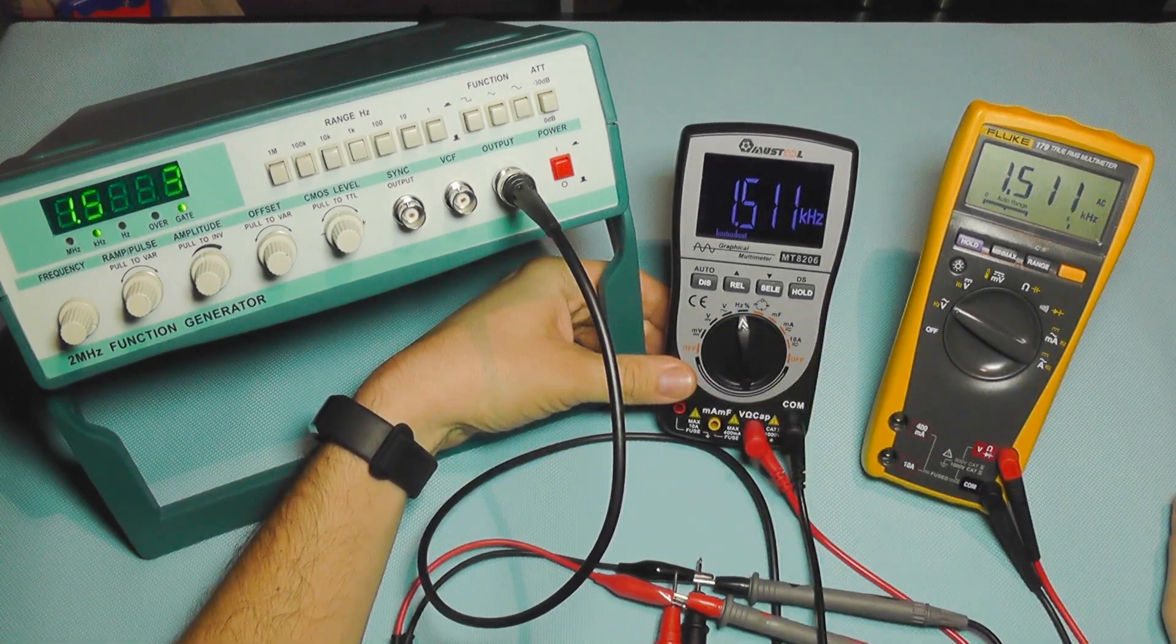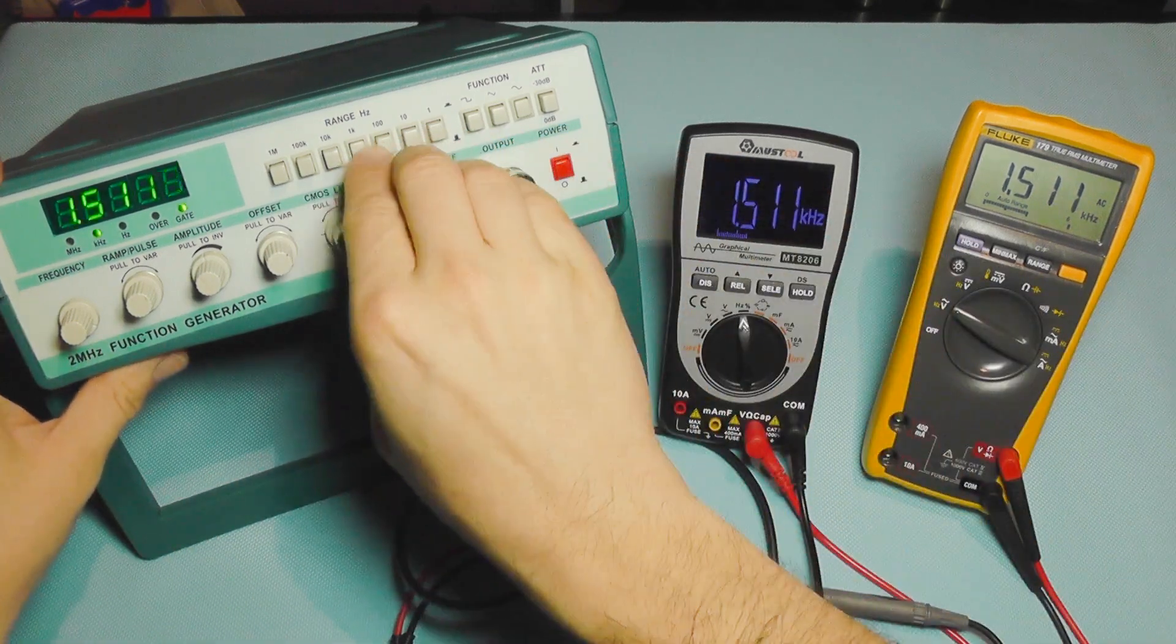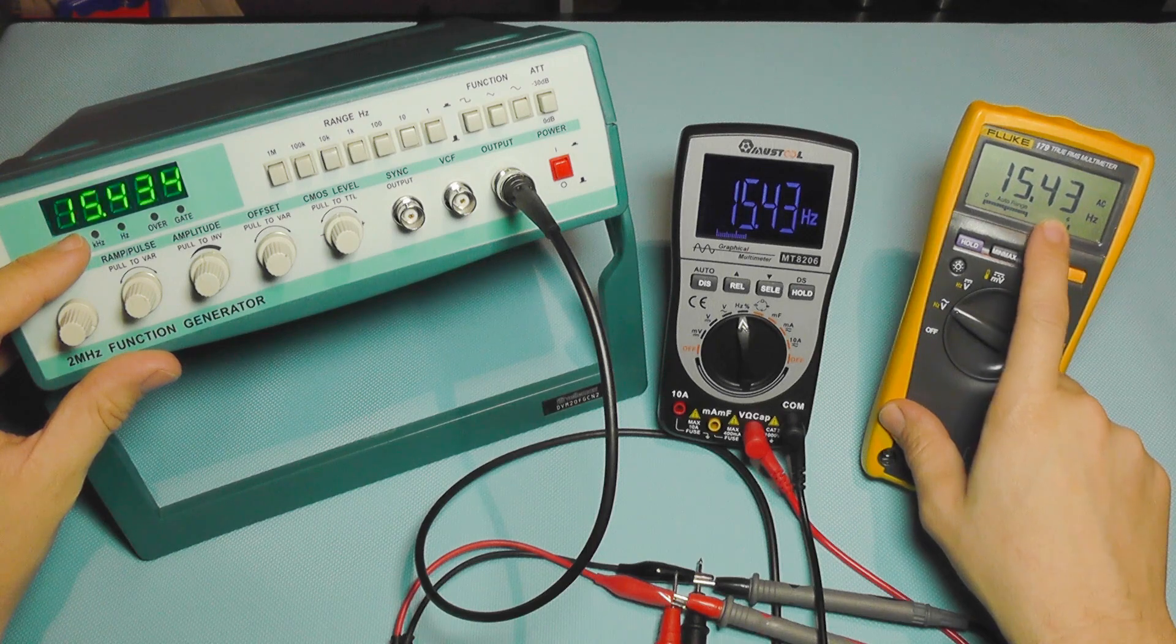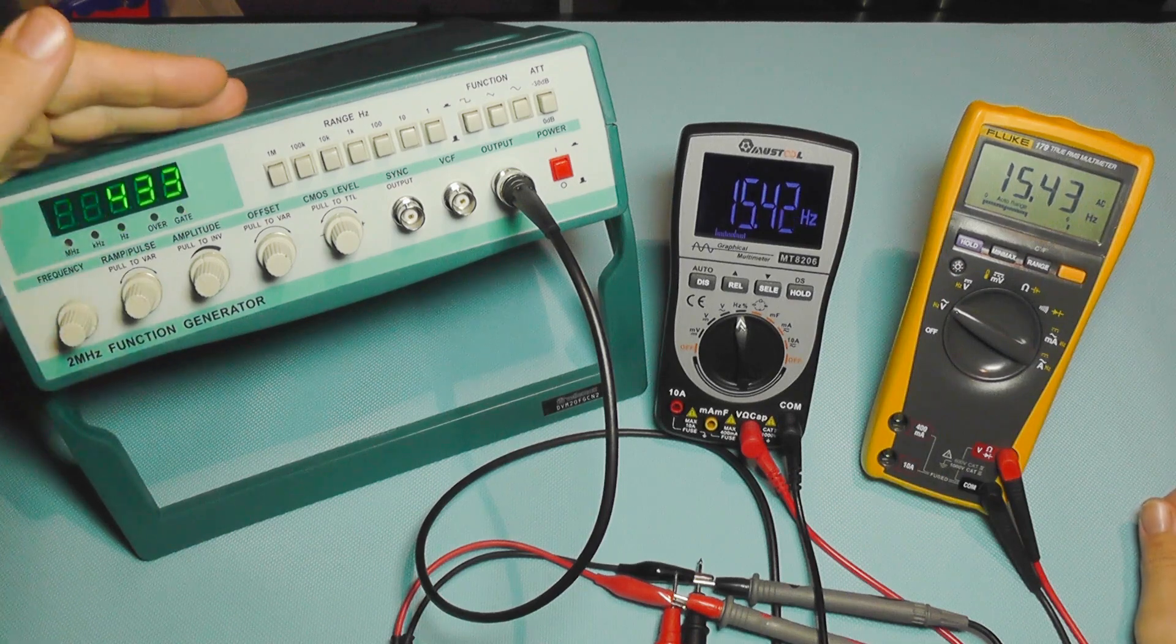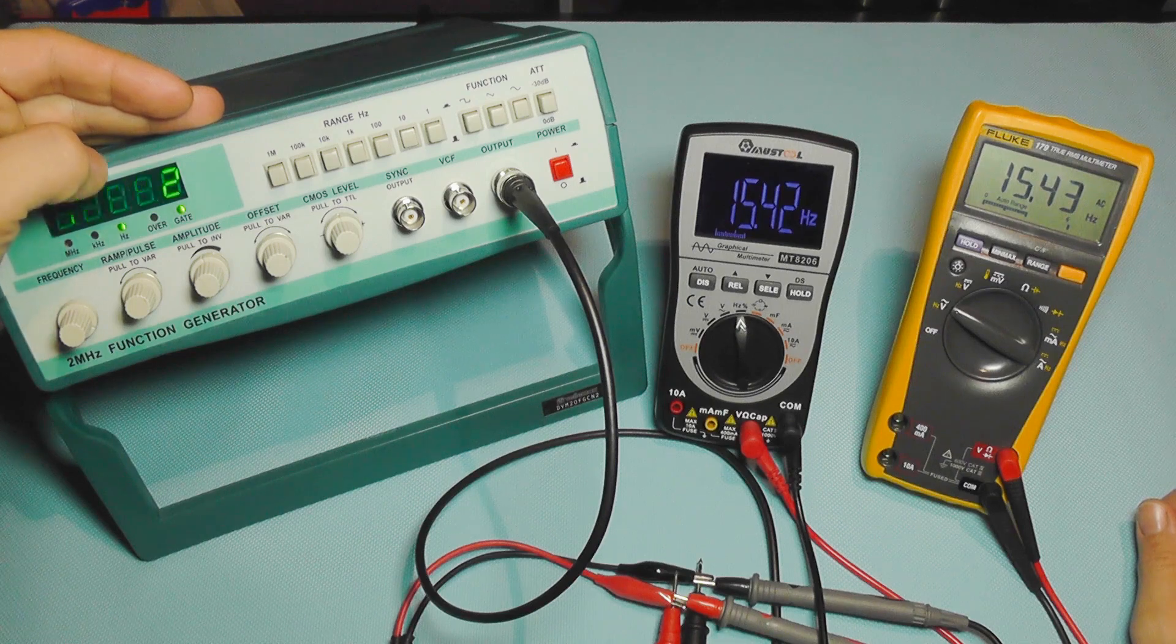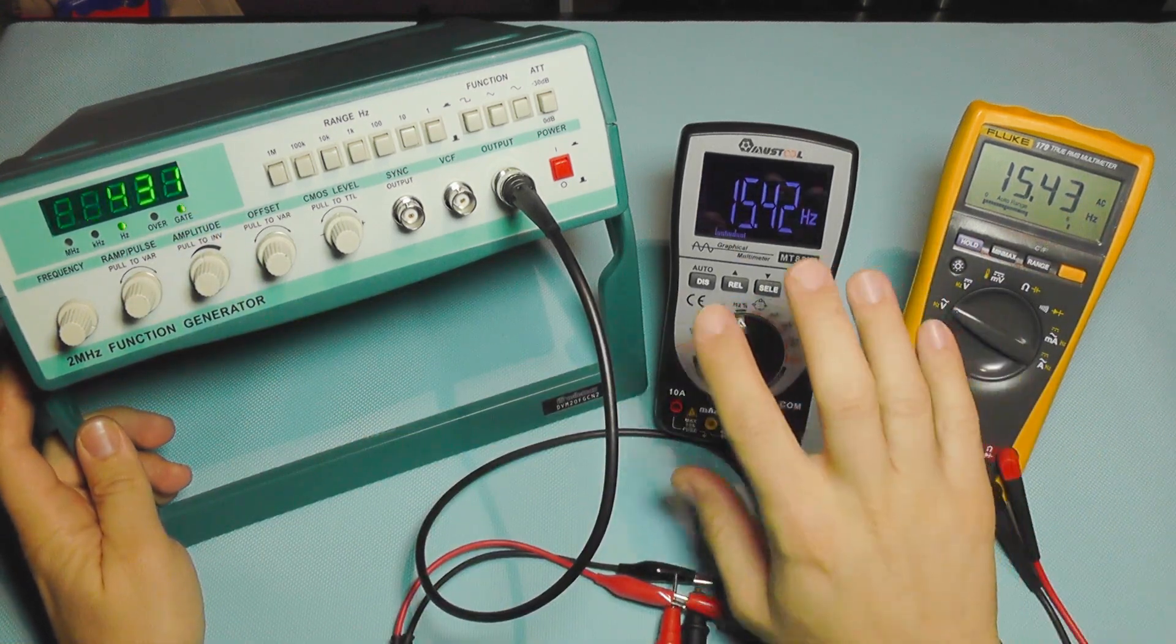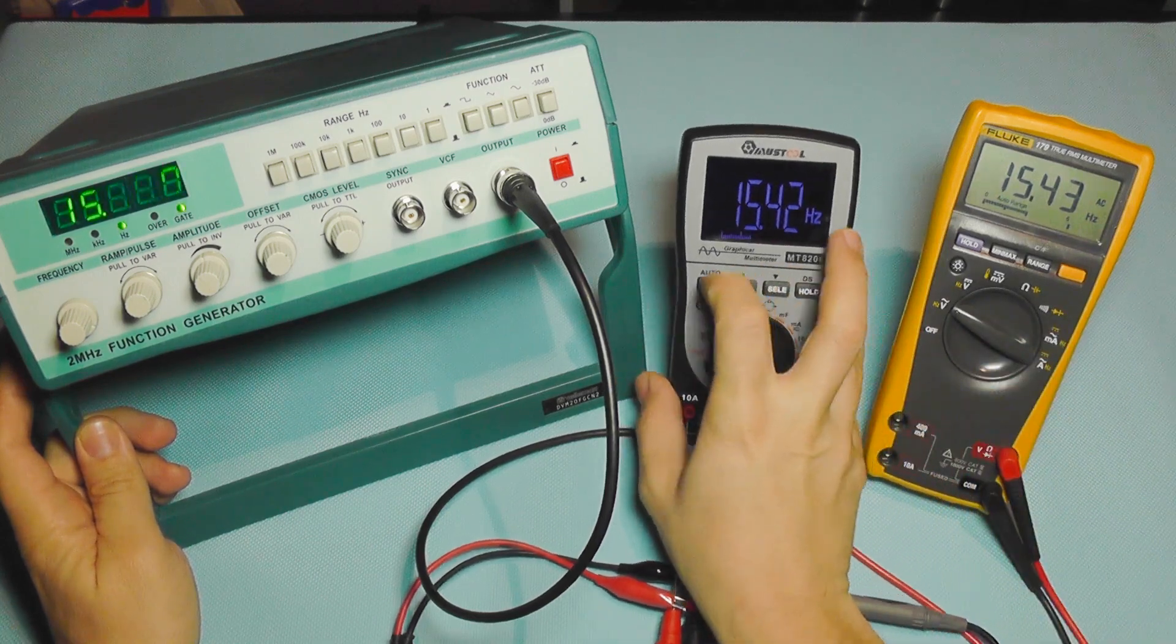So this shows frequency and I'm going to do the same for the Mustool. The frequency is identical on both meters. I'm going to try low frequency. Now it's 15 Hertz only. You can see 15.43 and 15.43, so they are almost identical, while the Fluke is closer to the signal generation. There is a small difference between them but not huge.